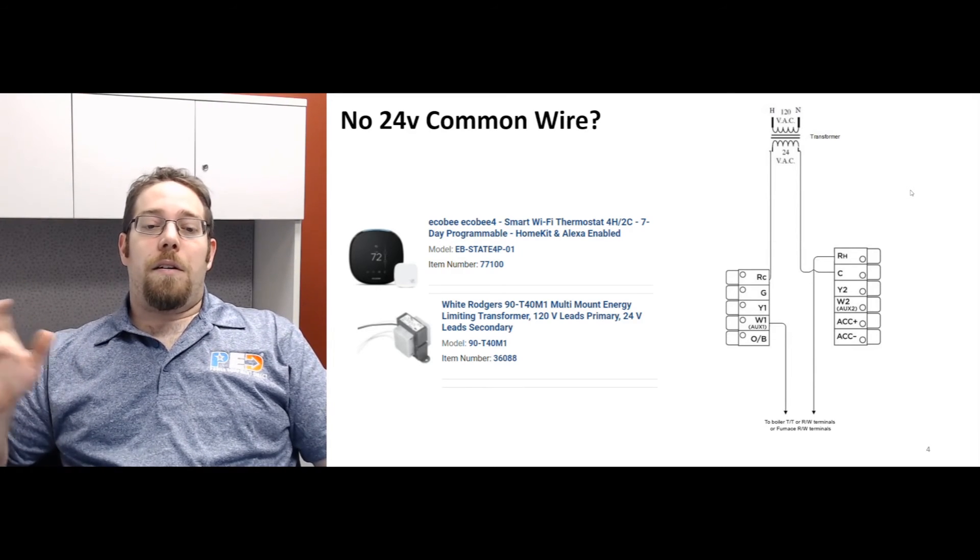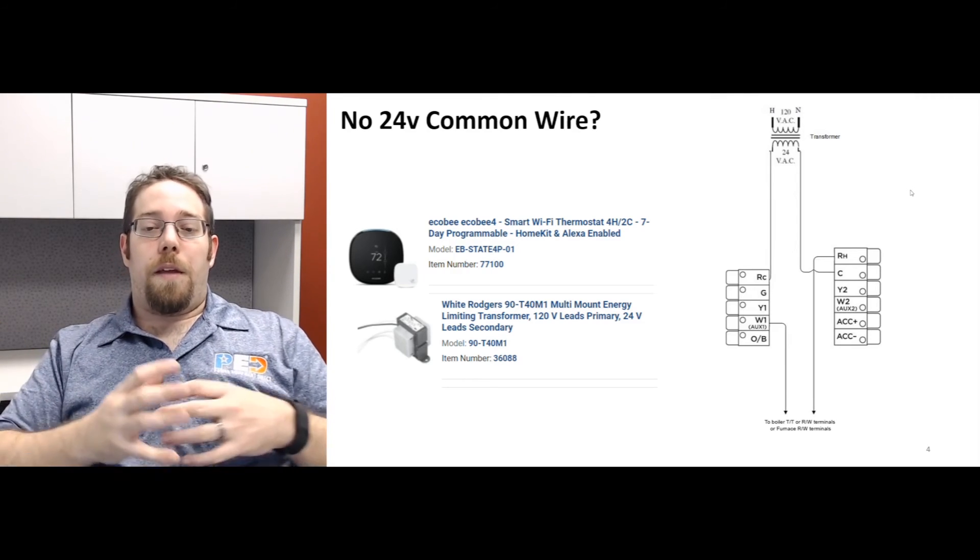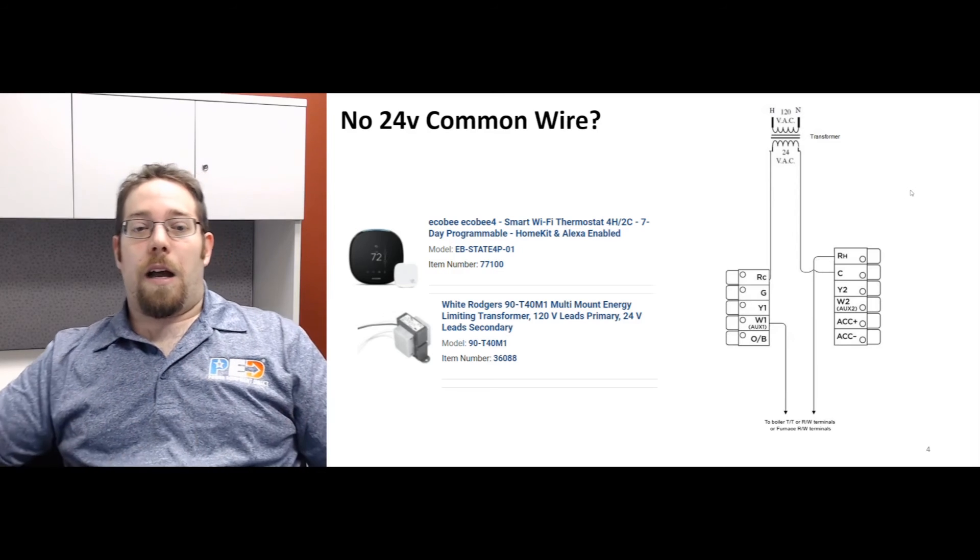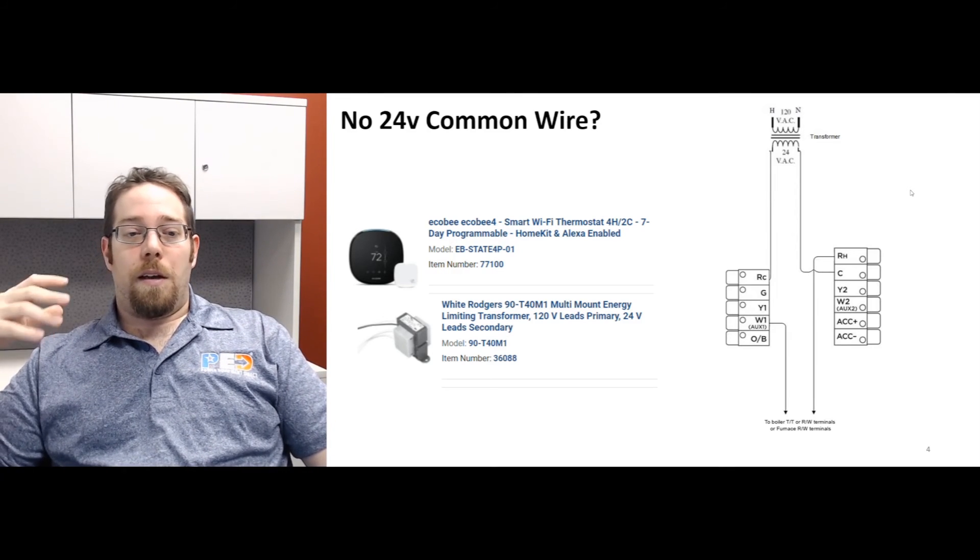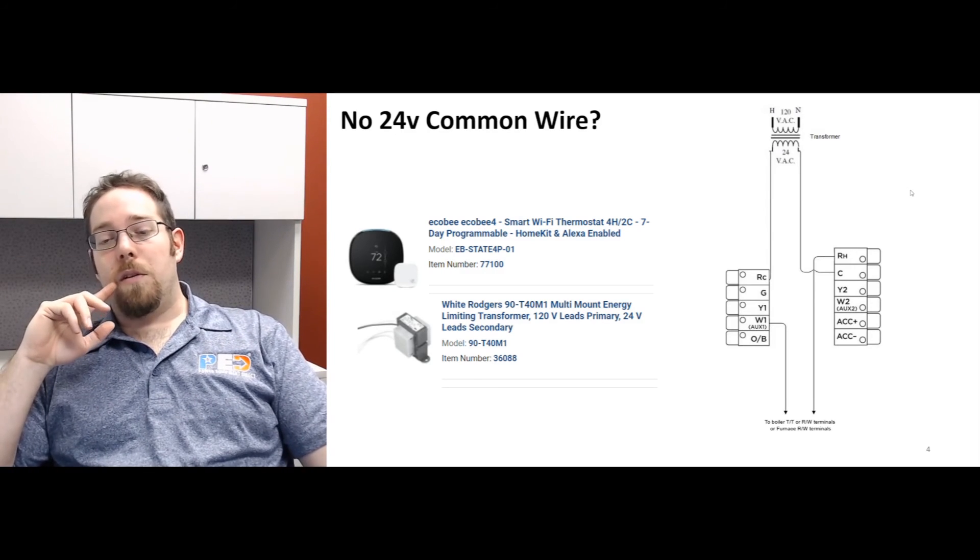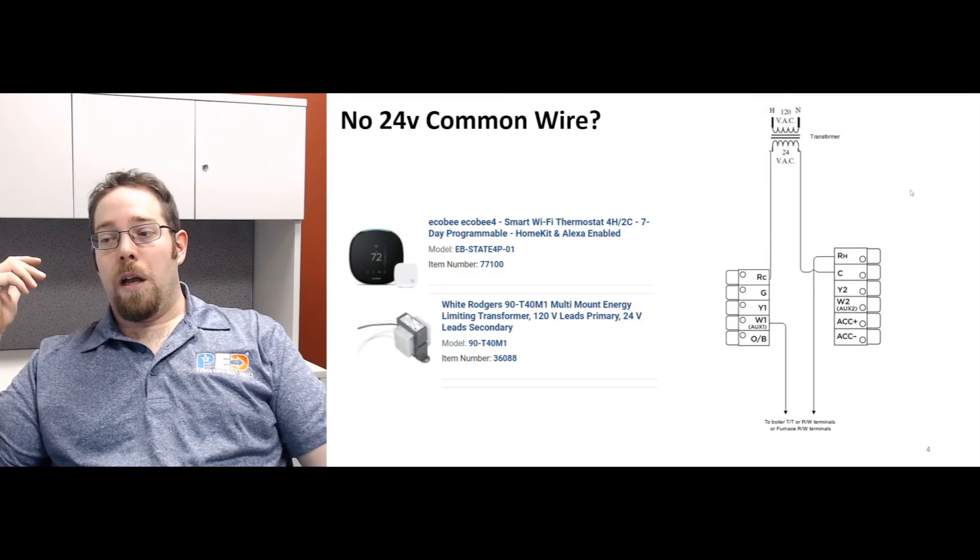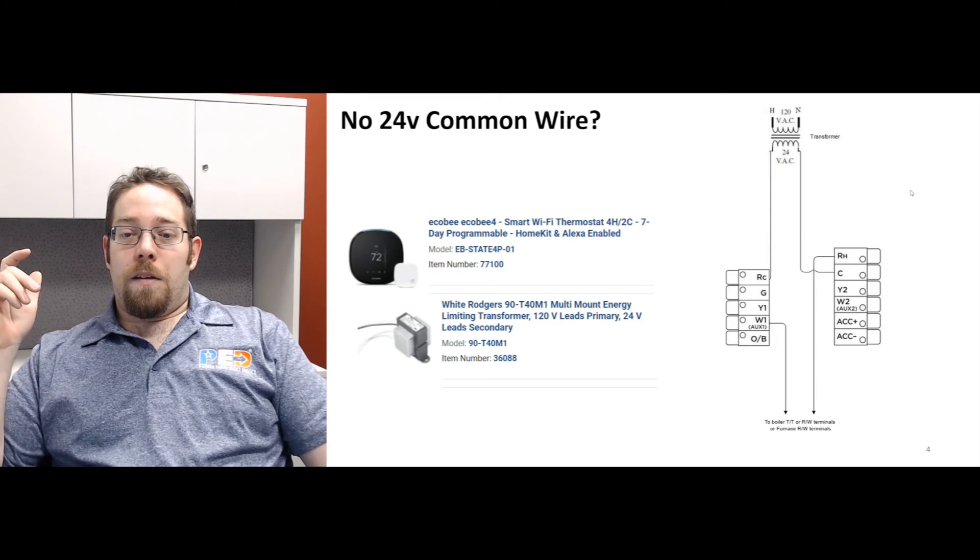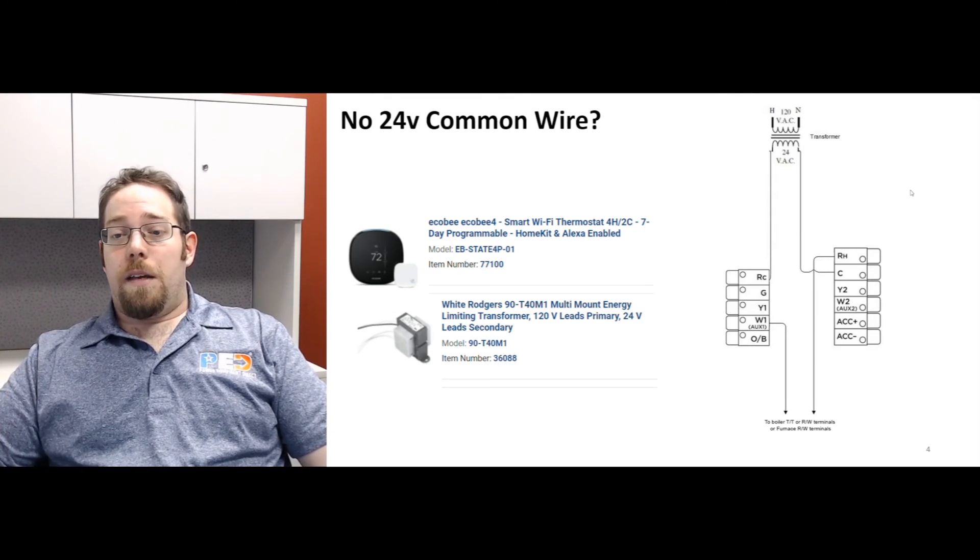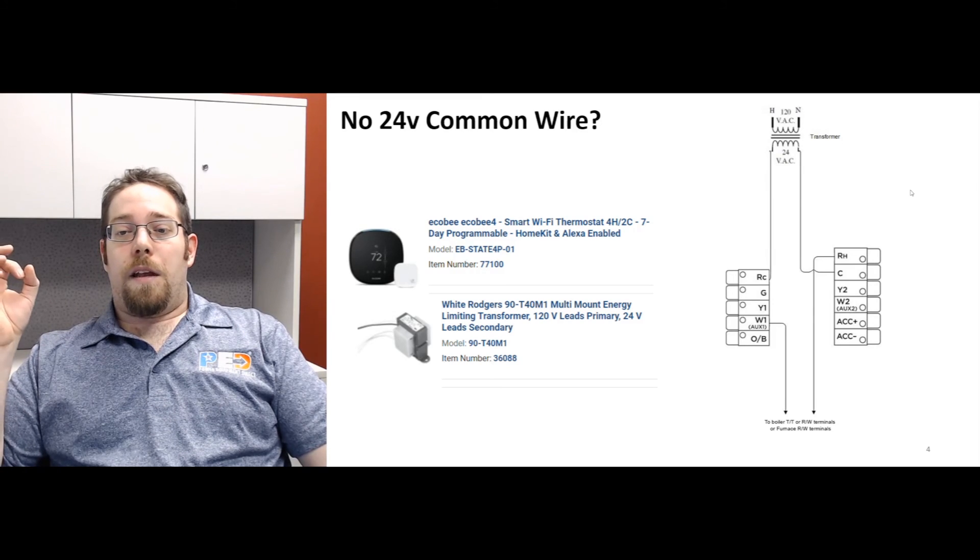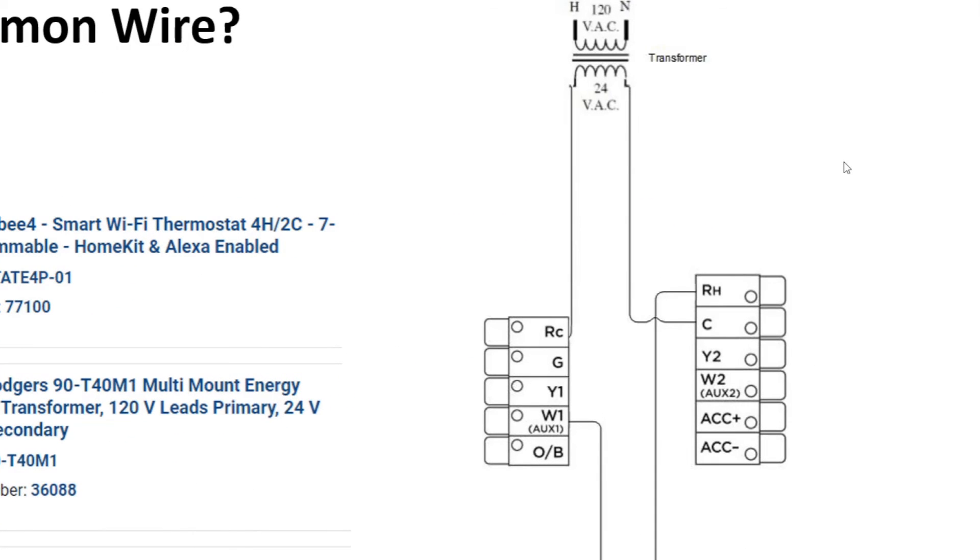So with that being said, you will need a transformer with the Ecobee. Ecobee does typically come with a connection on the unit itself, but it's going to be kind of the same concept is running the boiler in a way. So I know we did another one on the boiler, but you're still going to be connecting RH and the W1. So the RH in this case would typically be like the RC, and then you're going to have the C which is the common. And I know I have the wiring diagram there on your right, that's probably going to be your best help. On top of it you can still use the G, the G once again is going to be used for your fan.